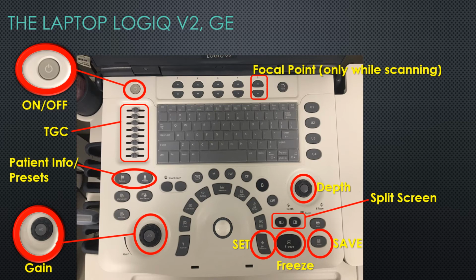So that's going to be your sweet spot where you want to try to put your anatomy of interest when you're scanning. But on these more expensive laptop machines, you have the ability to change the focal point. And the focal point really refers to the item that you're interested in clinically. So if you're scanning a heart one day, you might be looking at the papillary muscle and notice that the valve moves funny. And so you'd change your focal point to being just at the bottom of the valve. But if it changes all of a sudden to the aortic valve, then you might move your focal point up towards that aortic valve because now you've changed your focal point. You can't do that with a handheld. It's always locked in the middle point.